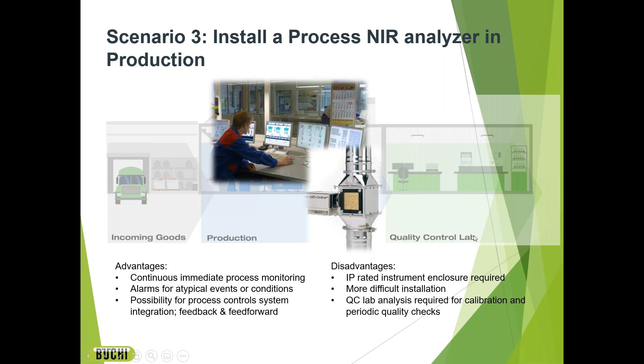Let's talk about the heart of the matter: NIR calibrations. The NIR calibration is what allows us to unlock these applications. The analysis speed we all want from NIR can only be achieved when the instrument is properly calibrated, and calibration involves collecting a lot of different variations in your process — different feed streams, seasonal variations, etc. BUCHI has a solution for all of this, working with customers to develop it.